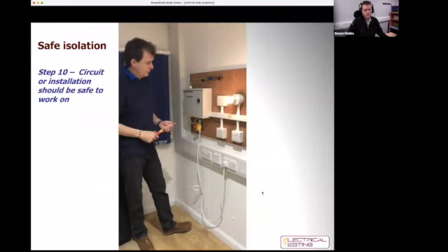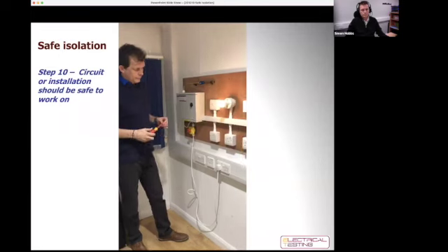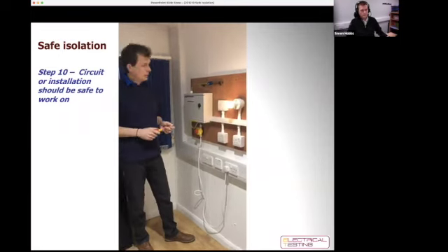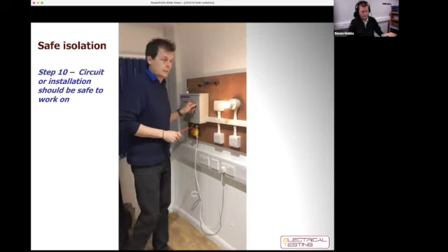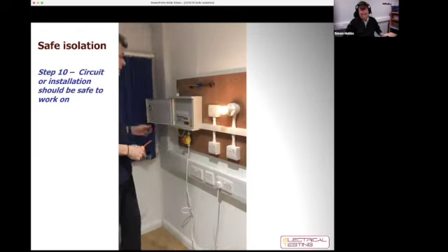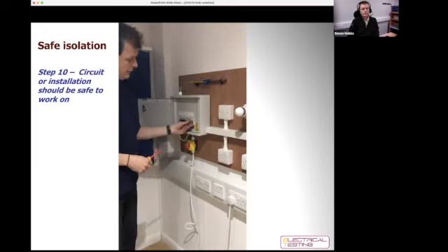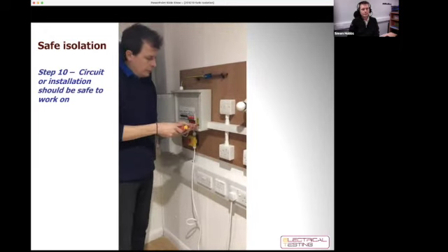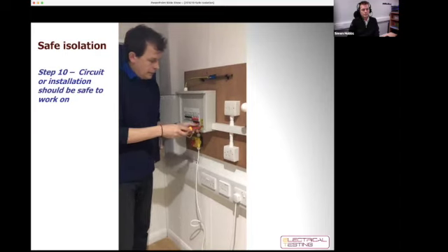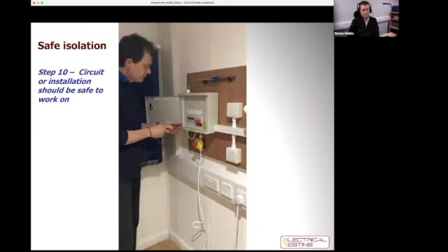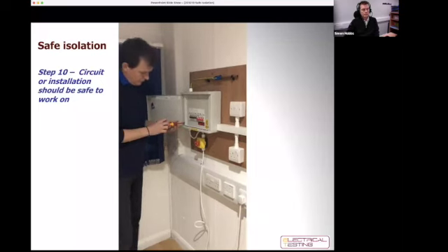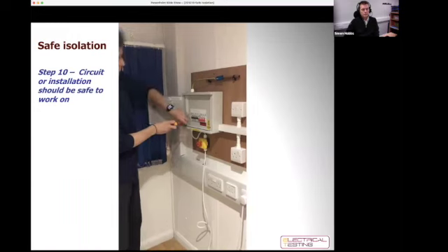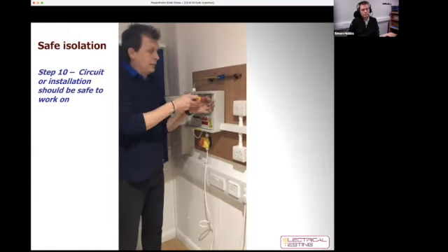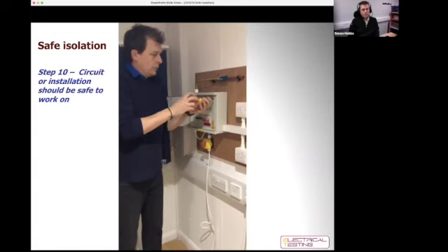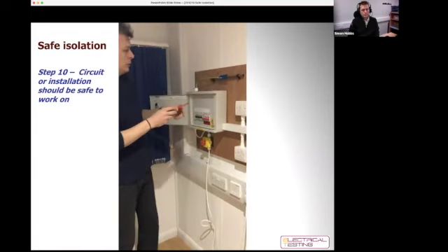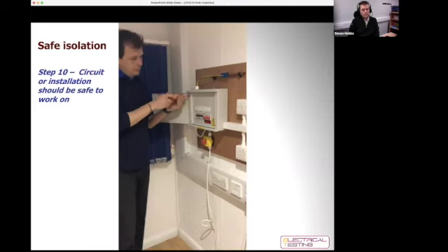Okay, Simon, we're here today to perform the safe isolation process on a 3-phase distribution board, please. Thanks, Carl. Have I got permission to switch the installation off? You're good to continue. Okay, so I'm going to take it off load and then isolate the main installation. As a skilled person, I am in control of the installation. So you're okay to remove the cover of the distribution board in order to move to the next step? I know where the live parts are and I'll be expecting them to be shrouded to IP2X. If not, I'll deal with that as I come across it at that time. Thank you.